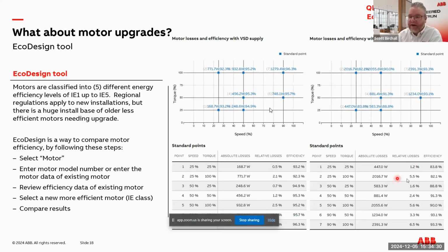But again, I can compare this old motor to the new motor. I can see the watt difference at these different load points. I can estimate how often it runs at these different load points. I can do the math and get a ballpark on what my return on investment would be. The first tool was about adding a drive in the first place when there was no drive. This one is about upgrading my motor when I had an older motor, maybe an IE2 motor to an IE5 motor.